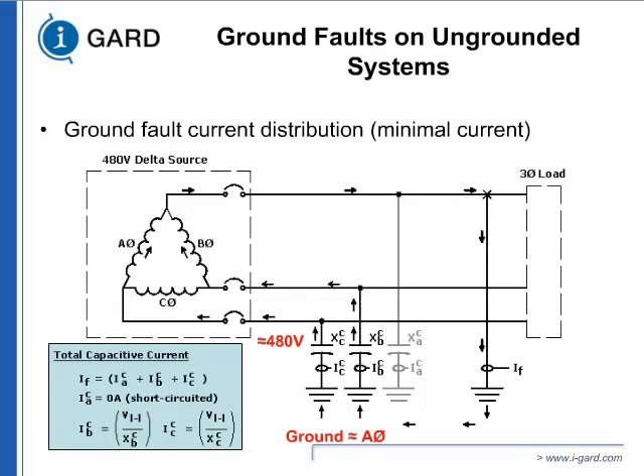And that was the reason they were used in the past, because you may have heard the expression, the first fault is free. That means the first fault did not interrupt our system. That was the primary reason in the 40s and 50s, before high resistance grounding came in, that Delta systems were so popular, because you could ride out the first fault. The system did not shut down automatically. If process continuity was important, you depended on an alarm to take the fault off if you could.